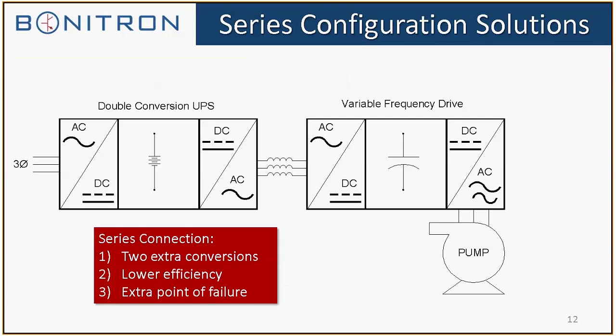With most of the other ride-through solutions, it's going to be a series connection. As you can see, there are double conversions there, so there are efficiency losses, and there's also an extra point of failure. Everything that goes to the front end of the drive is fed into the double conversion UPS and sent out directly to the drive. So if for some reason the UPS fails, it can take out the whole process. Now, there is bypass circuitry in most double conversion UPSs and series ride-through, but that's still a series path, and when you're in bypass, you don't have the backup protection.